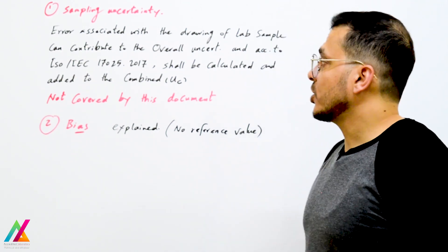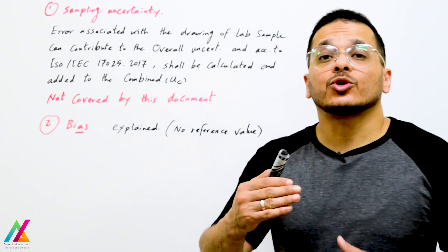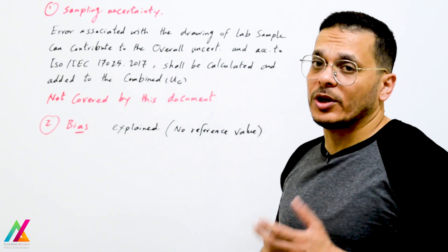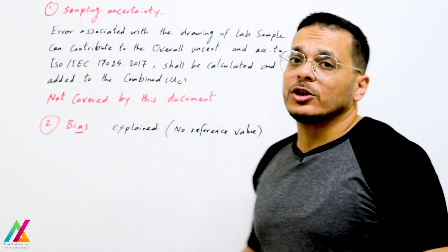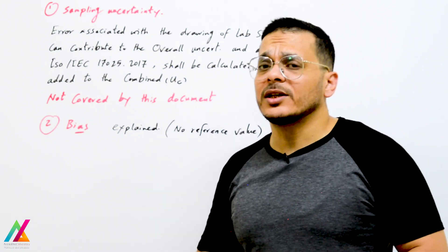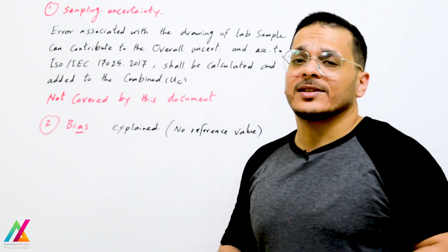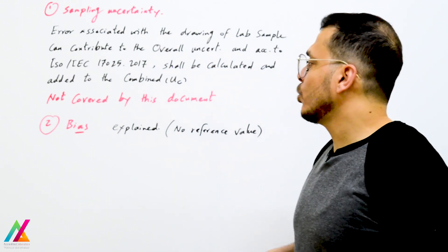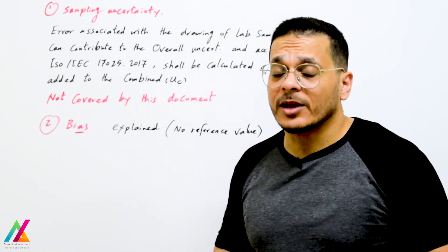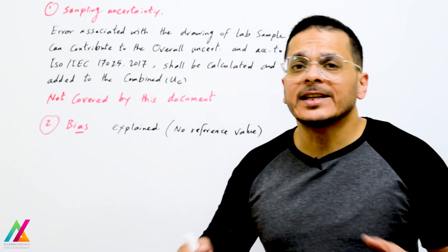First, sampling uncertainty: errors associated with the drawing of the sample, transport of samples to the lab, storage, and everything can contribute to overall uncertainty. According to ISO/IEC 17025:2017, it shall be calculated. You have to calculate measurement uncertainty due to sampling, and that is covered in the NORDTEST and Eurolab guidelines, which explain how to calculate measurement uncertainty in detail.